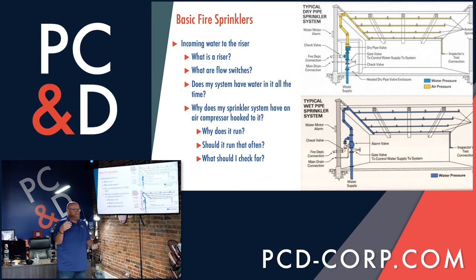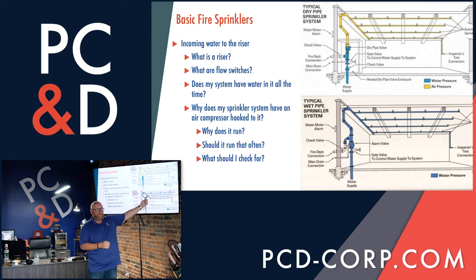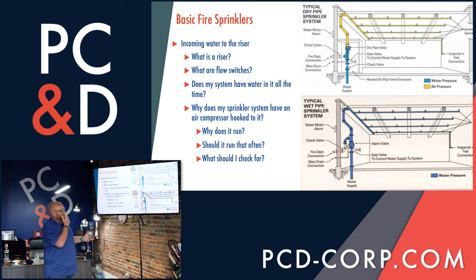You might be asking yourself, isn't a wet system better? When a head pops, you have water there instantly. If you've got air in there, how long does it take your water to get there? Again, that is an engineering calculation. So the water coming into your building has to reach the furthest point, the furthest sprinkler head, in 30 seconds or less. All of that's done on basic math or engineering calculations to understand how much pressure you have to reach that furthest point. If your water pressure coming into the building isn't enough to reach that furthest point in 30 seconds, what do we do? We've got a couple things that we can possibly do.